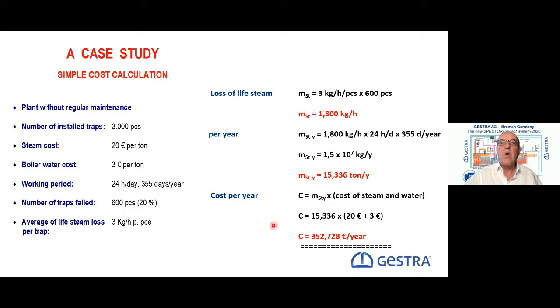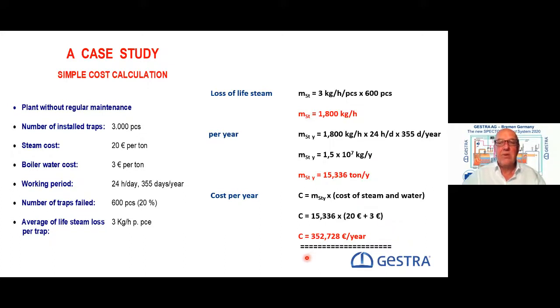Then we can calculate what this is in money. This is around about 1.8 tons per hour, 1,800 kilograms per hour. In 1 year, it's 15,336 tons per year. And that means at the end, multiplied by our steam cost, we have 352,000 euro each year, which we lost on energy. And it is often not considered that this amount of money is so much from a small number of steam traps which are faulty.